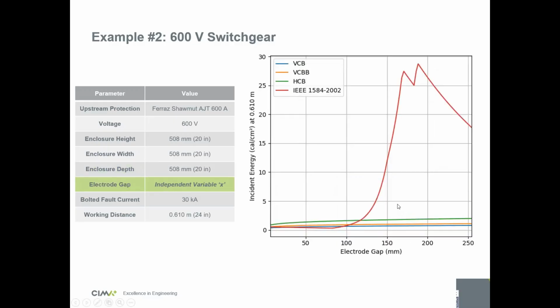And then electrode gap. You see here the last standard had a bit of a jump with the electrode gap, but this is because the electrode gap only went up to 150 millimeters in the last version. Now the standard goes up to 250 millimeters, but the past equations didn't go up there. So this is why you see a peak here, but it doesn't really apply because the model didn't go above 150 millimeters. This part of the red curve should not be shown because the past equations were not valid.